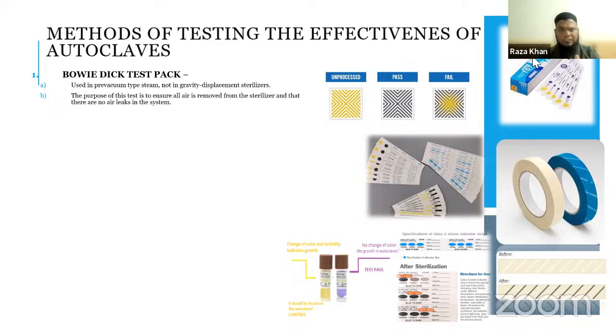So the Bowie-Dick test is primarily in this. You can see this Bowie-Dick test in which the yellow is unprocessed. Yellow color shows the unprocessed cycle. Complete black color shows that the cycle passed satisfactorily, and the partial yellow and black indicator shows that there is some air pocket or some leakage in the test. So the cycle is not satisfactorily completed.